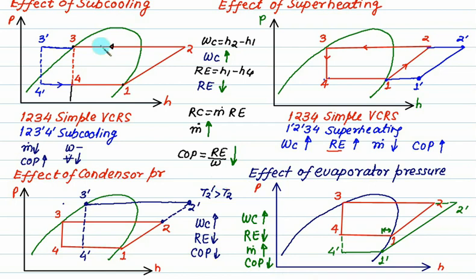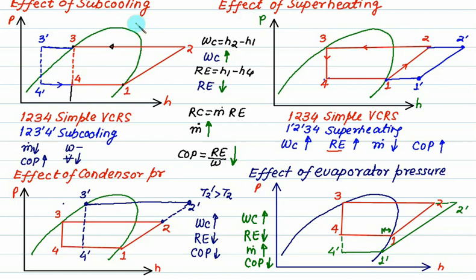The best VCRS cycle is sub-cooling plus super-heating, with a low difference between condenser and evaporator pressure. When evaporator pressure is not too low and we have both super-heating and sub-cooling, that is the optimal cycle for VCRS.